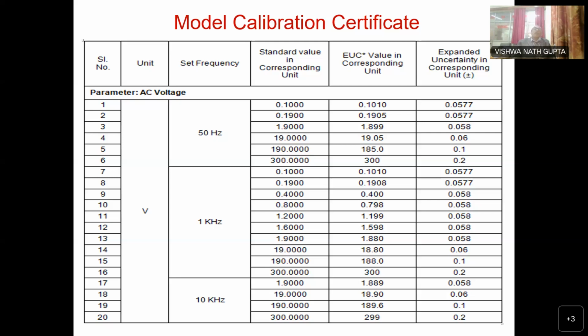Why that enabling document says, sir, that once you are going for the calibration or measurement of high voltage, your relative humidity should not be more than 60%. Here, we can control the environmental temperature very easily, but control of the humidity is very, very important.